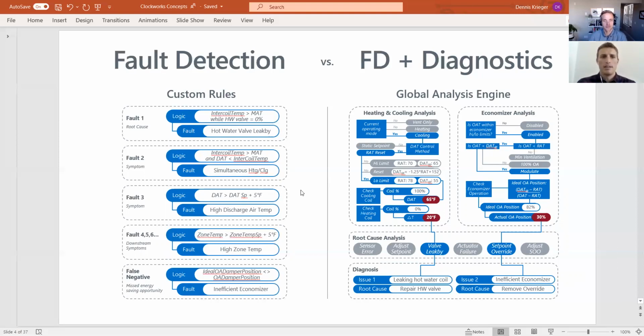It is, and I think the hardest concept to quantify here is this concept of a false negative. In our industry, this is one we'll never really be able to speak to and measure, because of the nature of a false negative. If you haven't taken into account, for example, that economizer sequence, and you're not checking the ideal outside air damper position to optimize energy performance, you may miss things like: this damper position isn't where it should be, and we could be taking advantage of free cooling on top of all the issues we're having with this hot water valve leak-by.